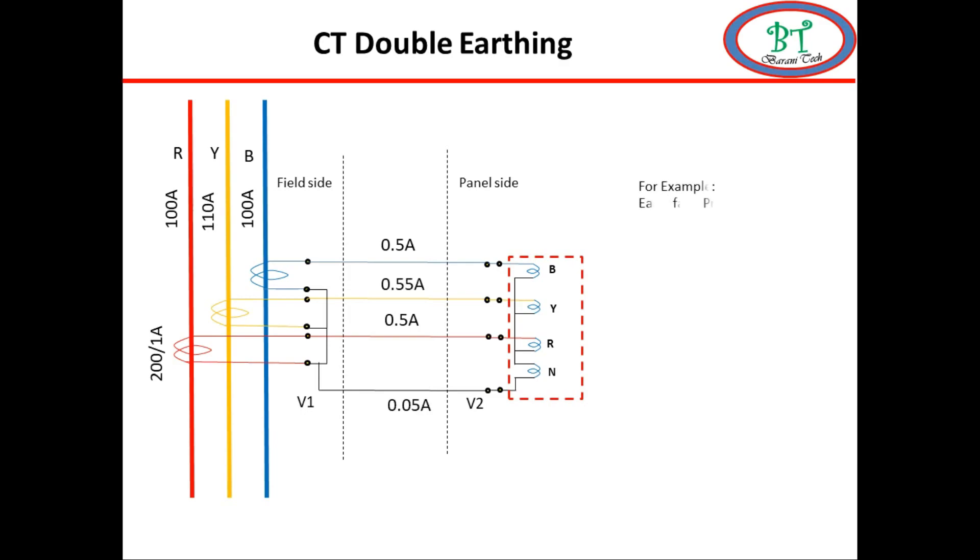Due to overload on Y phase will cause unbalance in three phase current, which lead to zero sequence current, which flow on neutral circuit of the CT. During this case the relay should not operate.